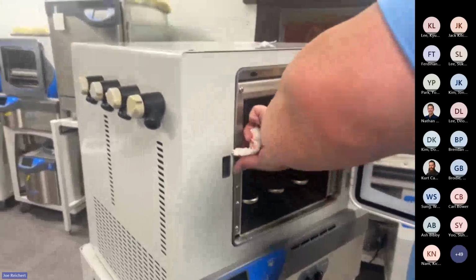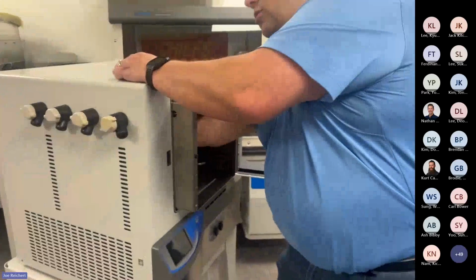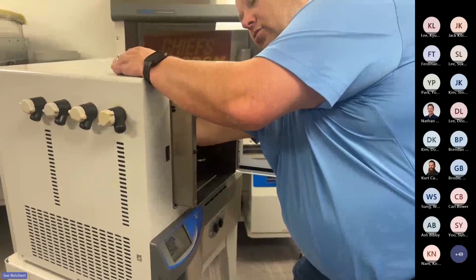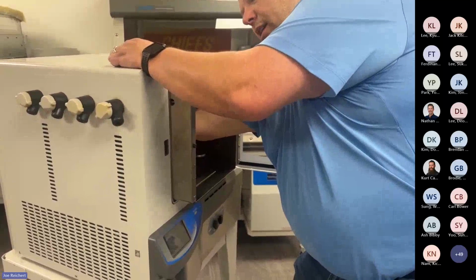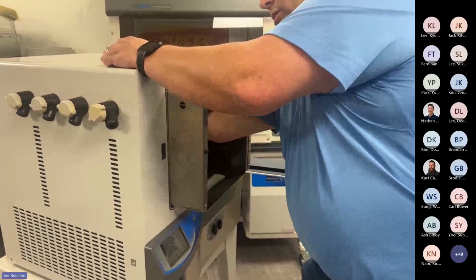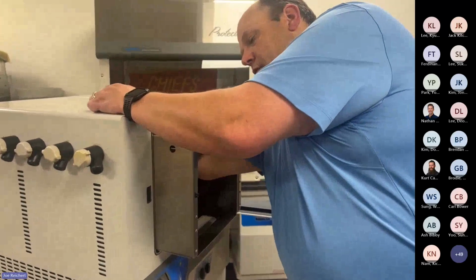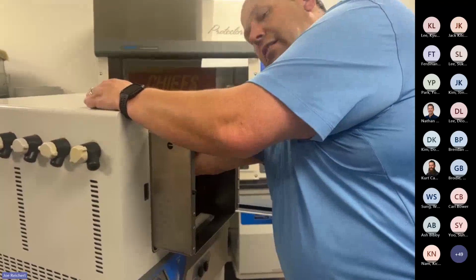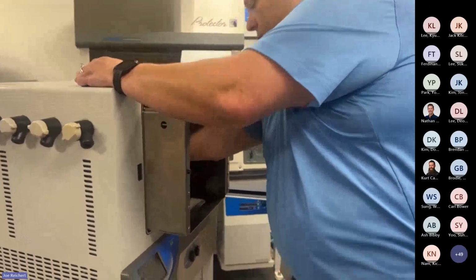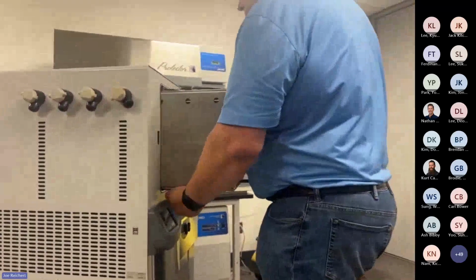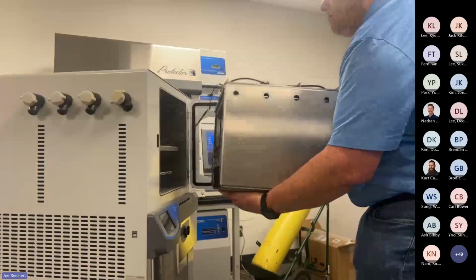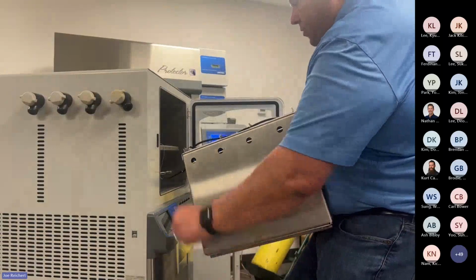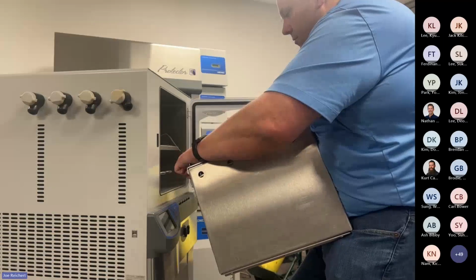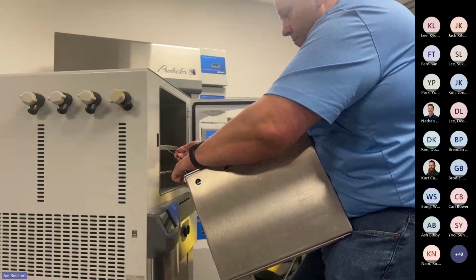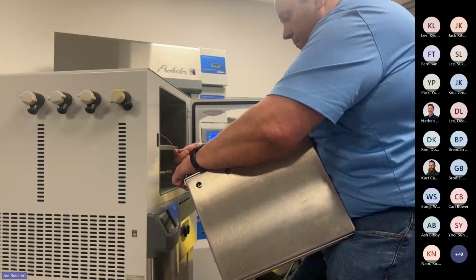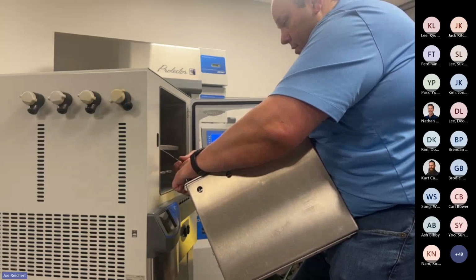To pull this chamber mechanism out, like I said, it's just pulling, but you have to deal with the wires here. You just want to make sure that those wires get disconnected. There's a pass-through in the back, top left corner where they plug in. And then you have the hose from the bladder that's also on the back, and it just slides off the pole in the back. There is a little spring clamp on there, which you'll see here in just a second. And you also have a temperature sensor I forgot to pull off here. And trying to get that separated.